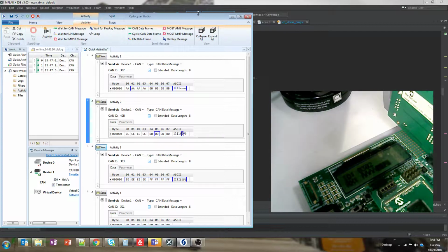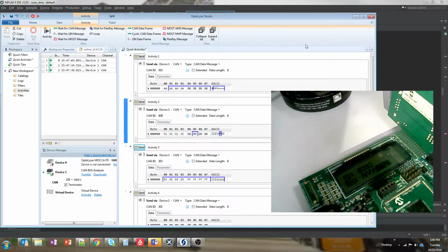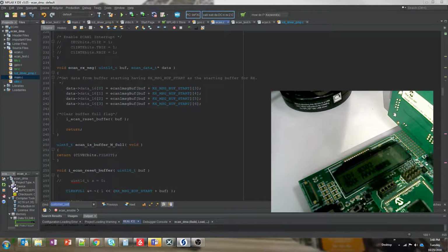This is the reason why in your setup you are seeing that the buffer for filter 302 is being corrupted, or overlapped, by the data that is being sent using CAN ID 303. The ECAN module was not able to filter it correctly because of the time quanta and the bit rate.